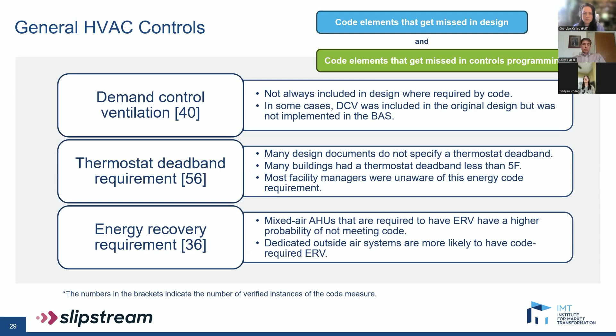And regarding the energy recovery requirement, we found that a lot of mixed air AHUs with high outside air percentages and high supply air flow rates have a greater tendency of not meeting code on this element. This is an issue that is typically found in the original design and then got carried out into construction, which seems to suggest an oversight in design. Dedicated outside air systems, however, are almost always found to be compliant with ERVs. So these measures are generally things that can get missed in design or in the controls programming when the building is occupied.